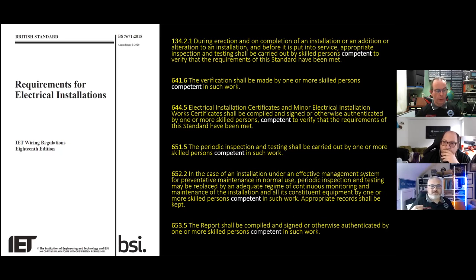The weirdest reg is 641.2.6, which is the second one. Verification being made by one or more skilled persons competent in such work. That to me is, well, you have the skills relevant to identify risk, but you're also very proficient in the application of understanding the risk in inspection and testing. And again, it goes full circle because the legislation looks for competency relative to the nature of the work.